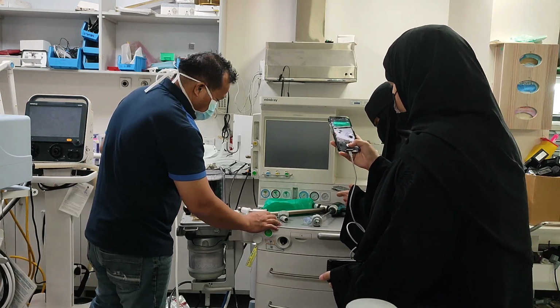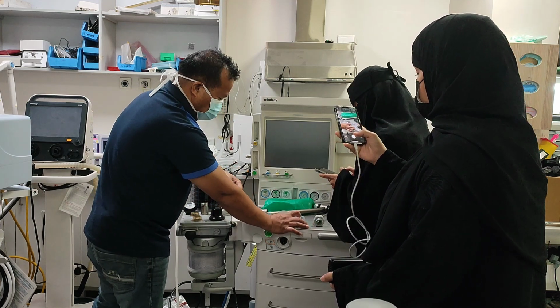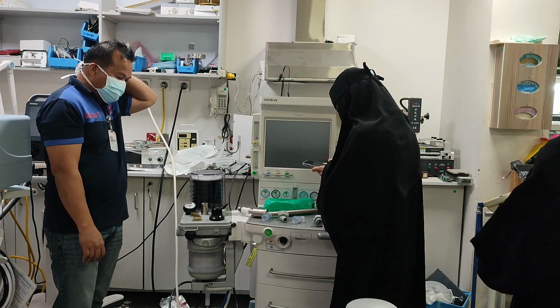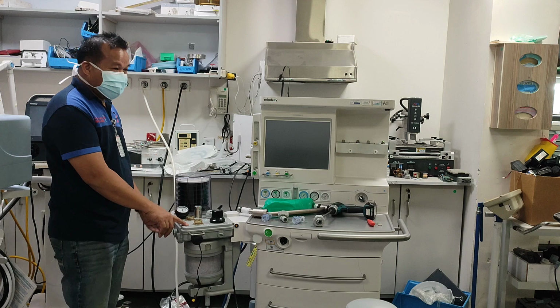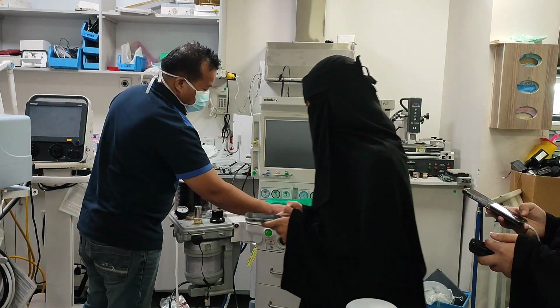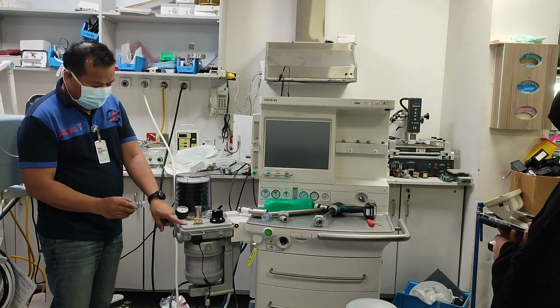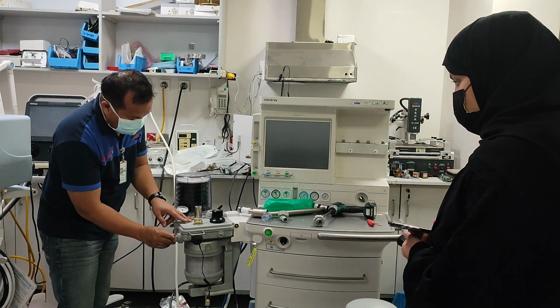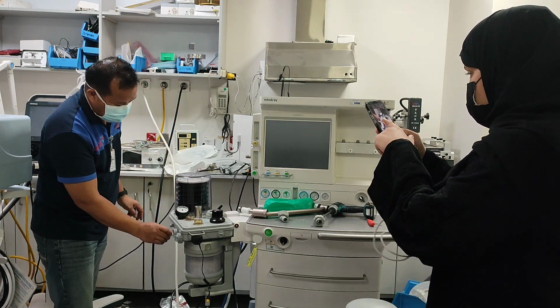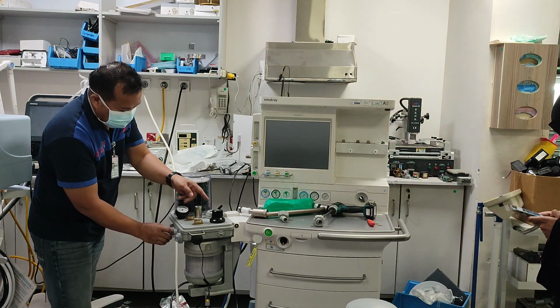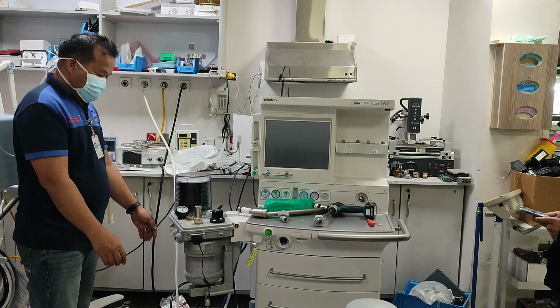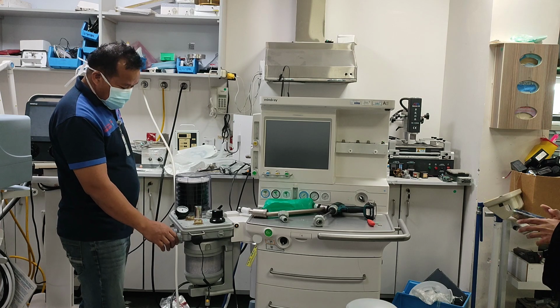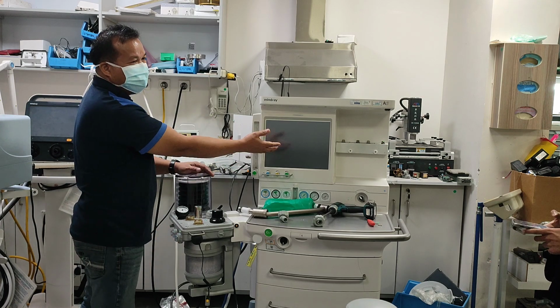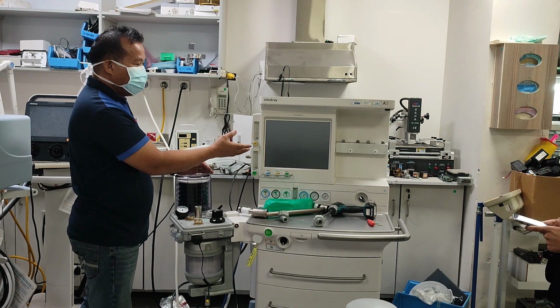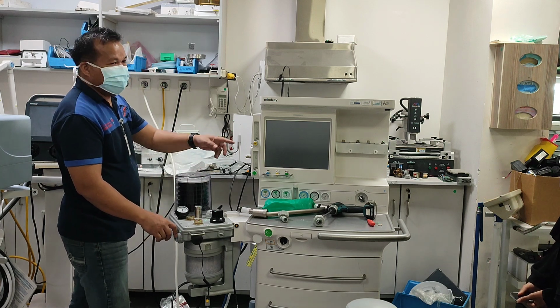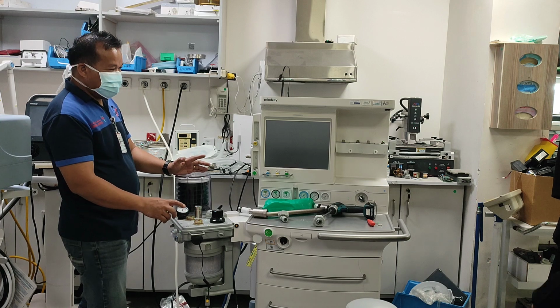If you see, there is an arrow. One is in, one is out. You cannot interchange them because of the arrow. For example, if you want to replace them, there is an arrow here, meaning this is the expired, out, and this is the inspired, going in. This is also important for service. If the tidal volume is not accurate, for example you set 500 and they are getting only 450 or 400, or more than 500, then there is a problem. You should calibrate only. Once calibration fixes it, it's good. But if calibration does not fix it, you should change this one.